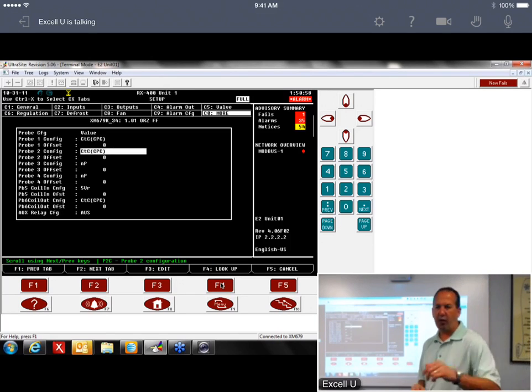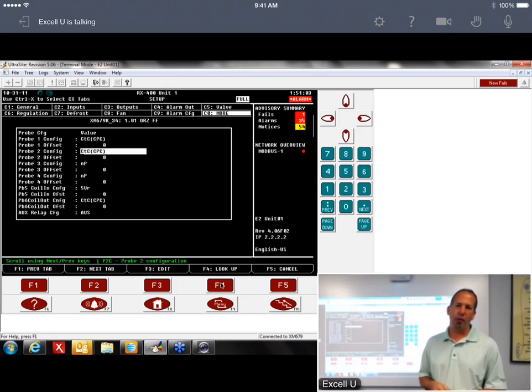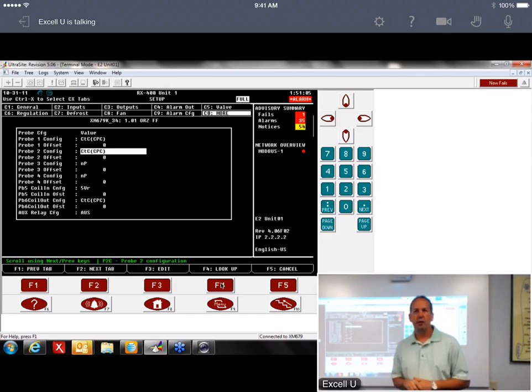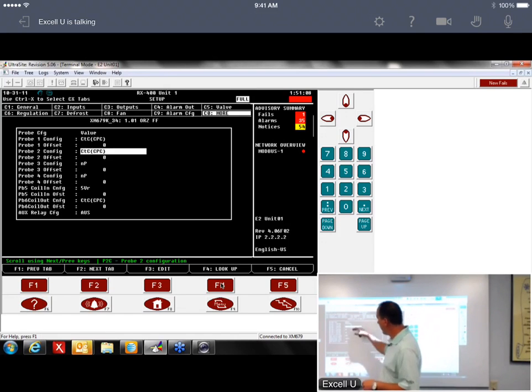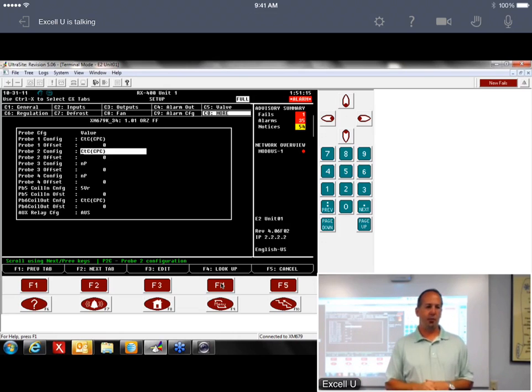Again, if you don't tell it no probe, it's going to populate your alarm log with a bunch of probe errors. So I highly suggest going and putting those in. Again, by default, they'll all populate as CPC probes, so you have to change it to no probe.